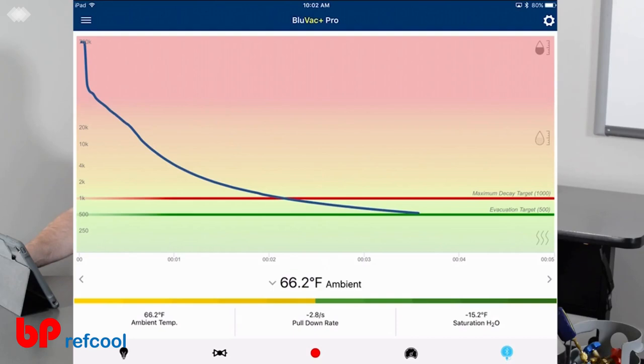We can see our ambient temperature 66.2. We can see our pull down rate, we're doing about 2.6 microns per second. We can see our saturation temperature of water, which is about negative 16. We can see we're at 495 microns. It's still coming down here. Let this continue to pull.